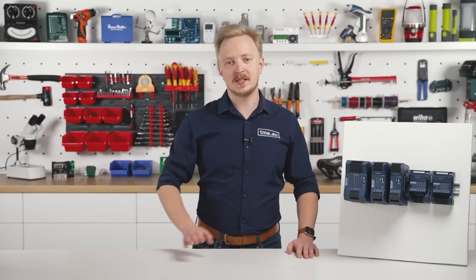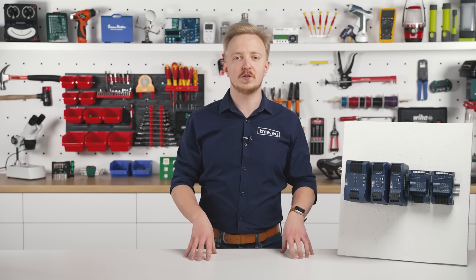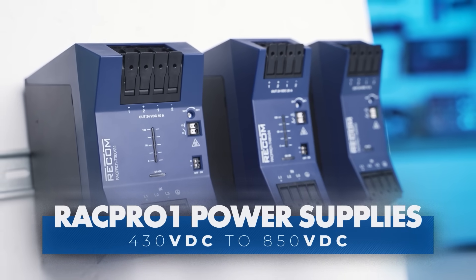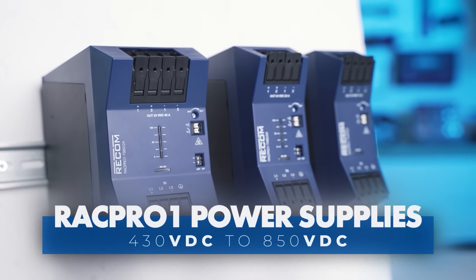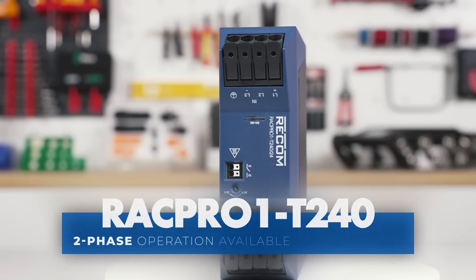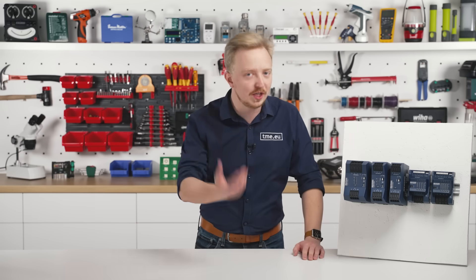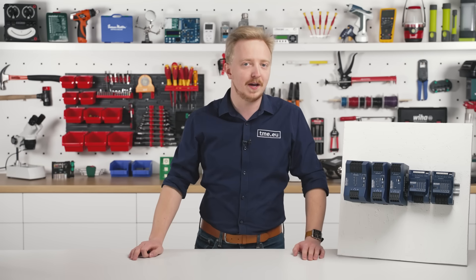The RACPRO1 Series power supplies have a universal AC and DC input voltage range of 3×320 to 3×575 volts AC and 430 to 850 volts DC across the entire lineup. The T240 model also supports two-phase operation from 2×350 to 2×575 volts AC, ensuring continuous operation without power reduction, even if one phase fails.